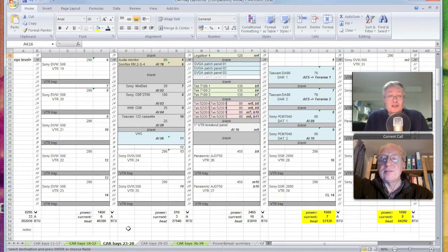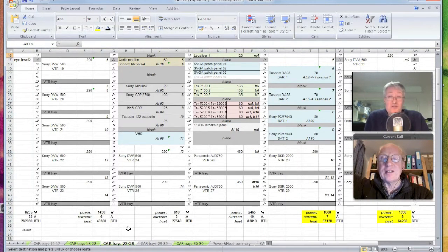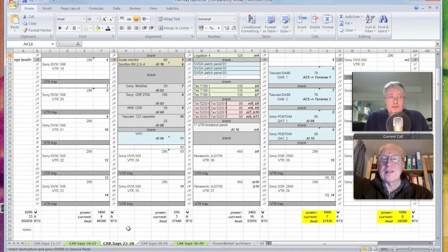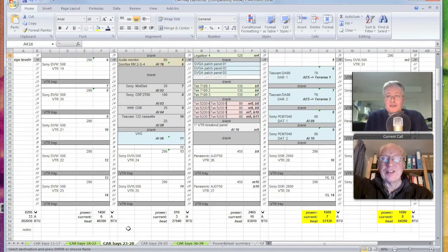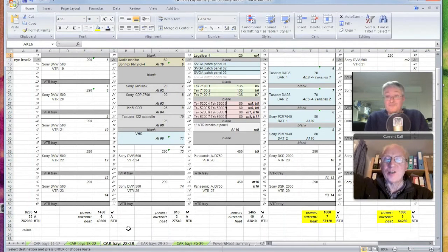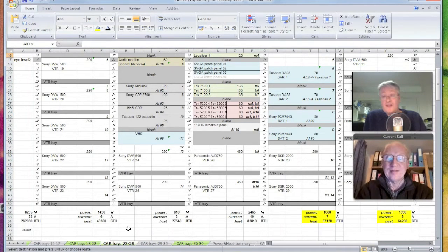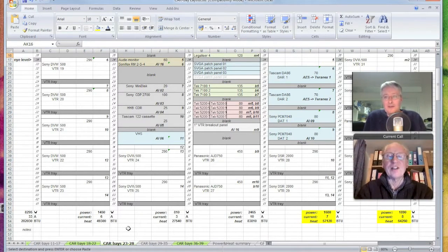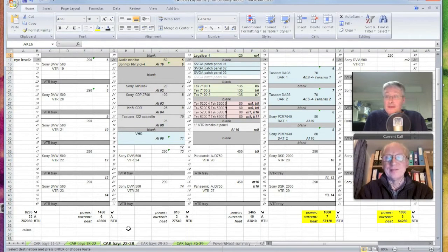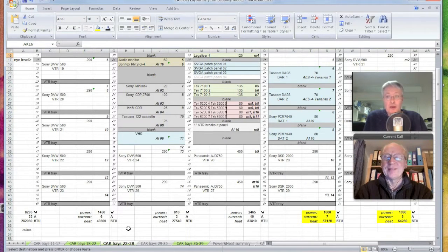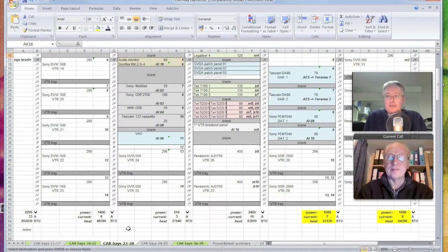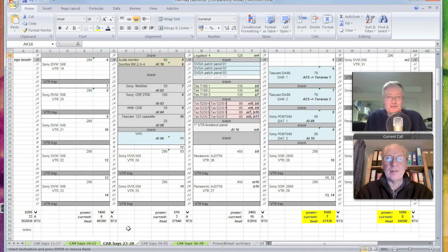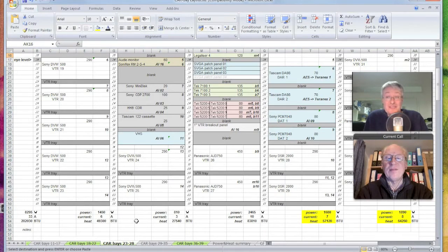But also it's useful to then be able to turn that into a heat requirement for the bay as well. So we knew for example that that machinery was notionally generating 82,000 BTUs of heat. And that's useful info for the aircon guy. Now people say, how on earth can you turn electrical power requirements into a heat requirement? Well I mean truth to tell, every piece of broadcast equipment, 99.9% of the power it consumes comes back out as heat. There's not very much power used to light the LEDs on the timecode counter on a VTR. There's not very much power that's actually being turned into video signals. I mean how many watts is a volt into 75 ohms? That's not a lot. And you're not whirling two-inch tape anymore so there's no actual motors.